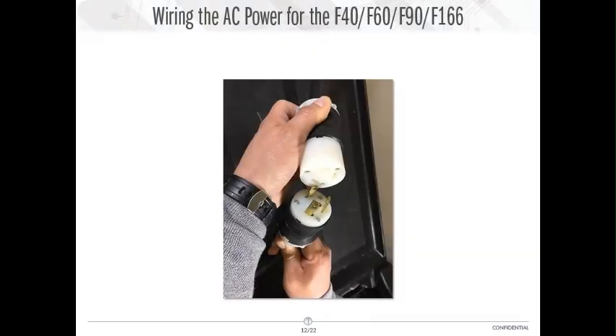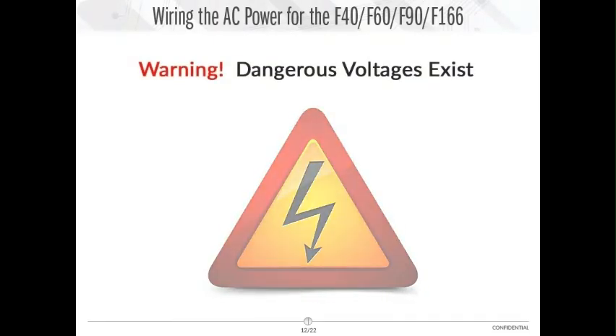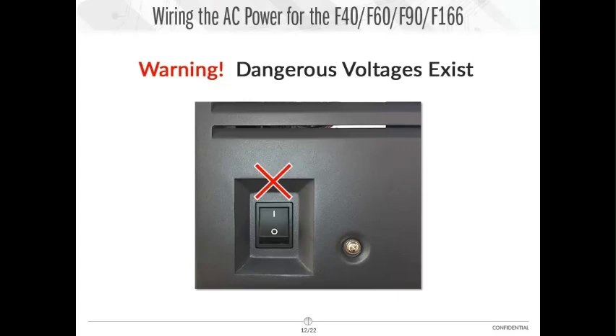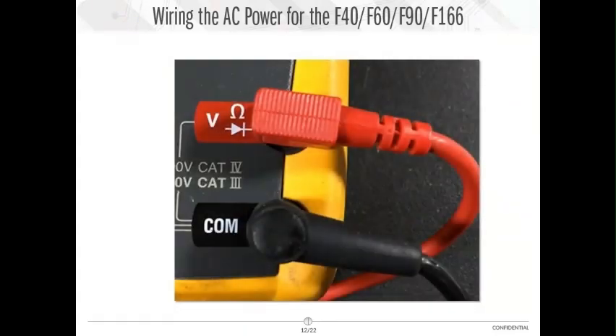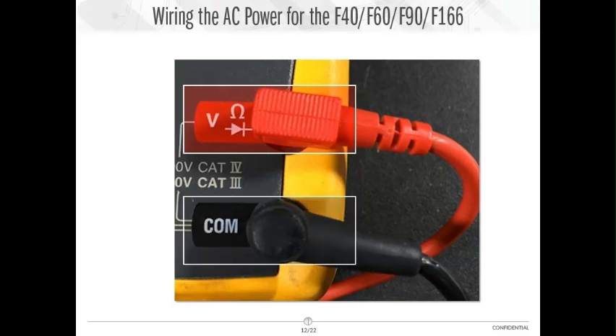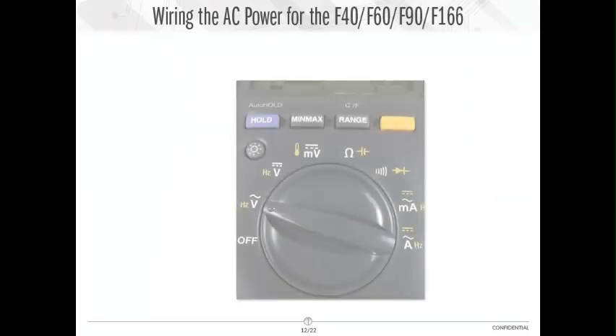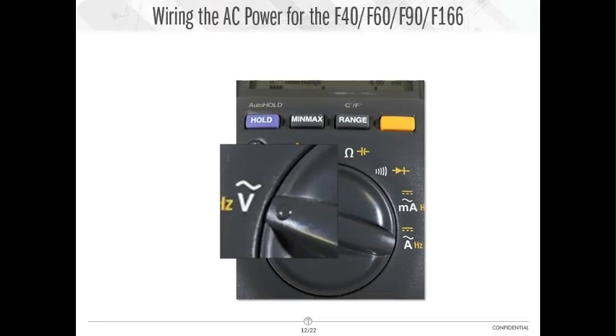Next, connect the pigtail to the receptacle or socket and verify the voltage at the printer. Please take care, as power is now present at the terminals on the printer. Do not turn on the printer before performing this step. Connect the red probe of your multimeter to the volt socket on your meter and the black probe to COM, or the common socket on your meter. Next, set your multimeter to read AC voltage.